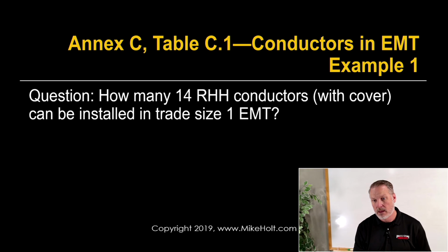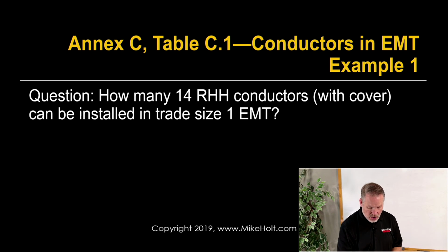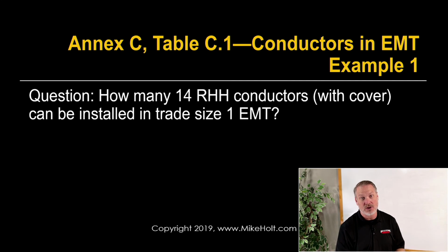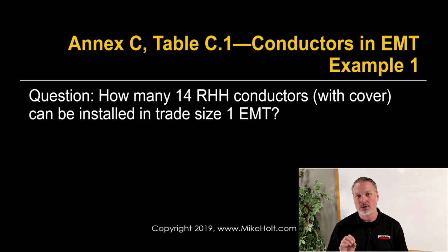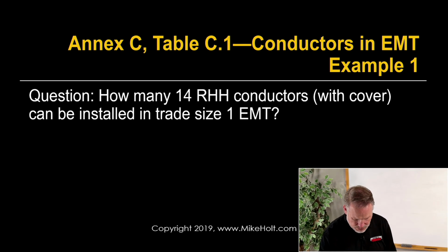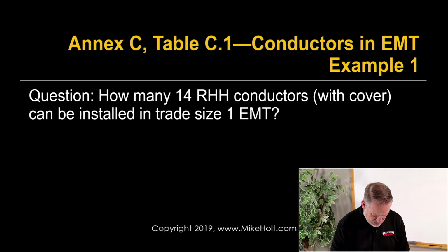11. Now, look about halfway down the page. It's got RHH with an asterisk next to that. What did we learn about that asterisk? Earlier it meant with the cover, right? Or I'm sorry, without the cover. And so here it actually means without the cover as well, but we don't have to assume that. We can always look that up, and if we just turn a couple of pages, we will find that the asterisk will indicate on there that that is without the outer covering.